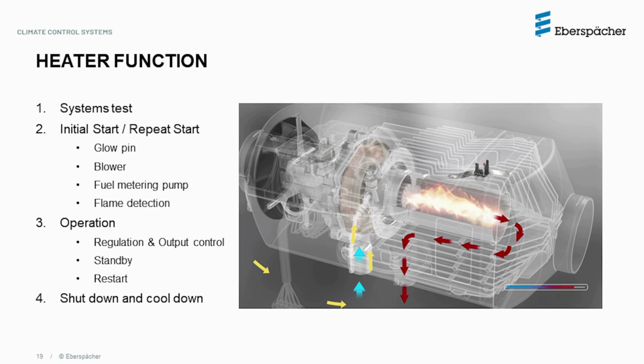The final phase of the heater is the shutdown and cool down process. In the cool down process, the blower fan will operate at a preset speed for approximately 4 minutes. During this time, the fuel pump will remain switched off, but the glow pin will be re-energized for approximately 40 seconds to burn off any residual fuel. If the power supply to the heater is disconnected during this phase, the heater will be forced to shut down immediately without cooling down. This can damage components within, especially the blower fan assembly.